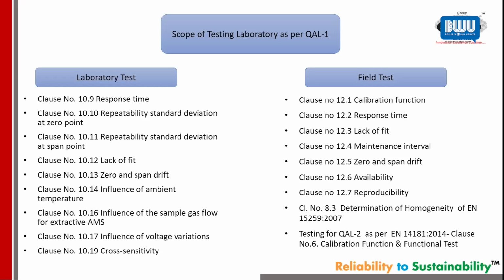That is not wrong also, subject to you having the test report of that, not the certificate page. I'm talking about the test report, where it is mentioned that the influence of temperature will give you this much tolerance or this much inaccuracy. So while you compensate in your reading, if I got 12, it should be 12.5, so I'll add that 0.5. That is not wrong also, but you should have the test report of the notified lab which has tested your equipment and certified that equipment. That test report should be available, which is not available. Because when you perform your next calibration or testing, you need that past data. The equipment was calibrated at what level, influence at what level, then only can I make a comparison of whether the deviation is there or not.